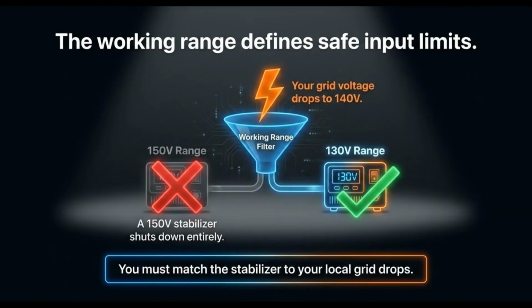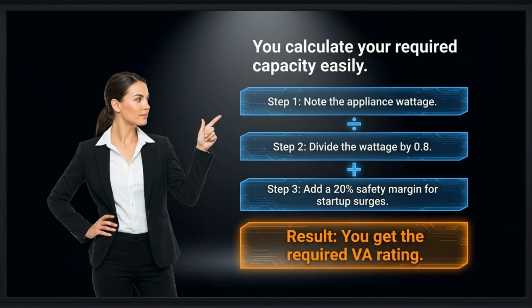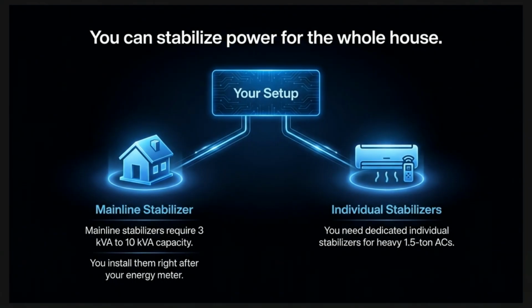The working range defines safe input limits. For example, a 150-volt stabilizer shuts down if the grid voltage drops to 140 V. You must match the stabilizer to your local grid drops. You can calculate your required capacity easily. Note the appliance wattage, divide it by 0.8, and add a 20% safety margin for startup surges to get the required VA rating.